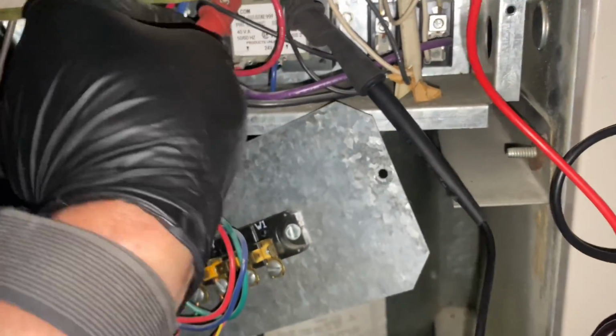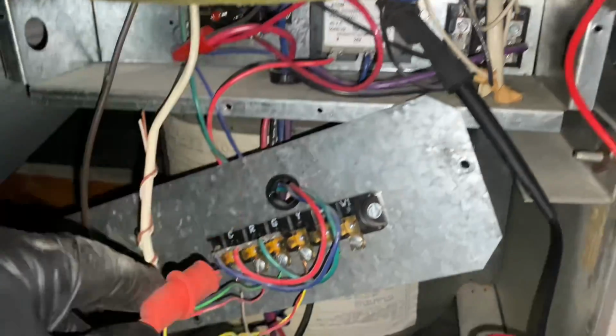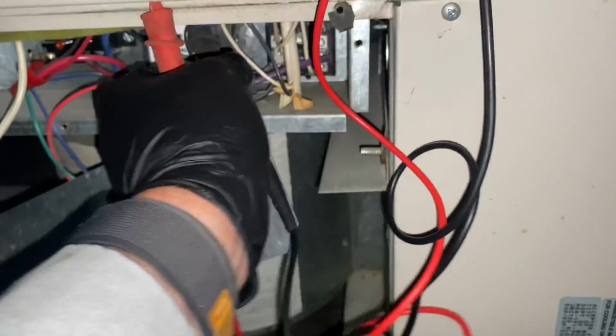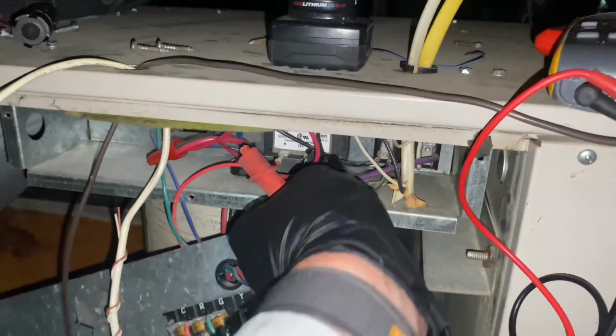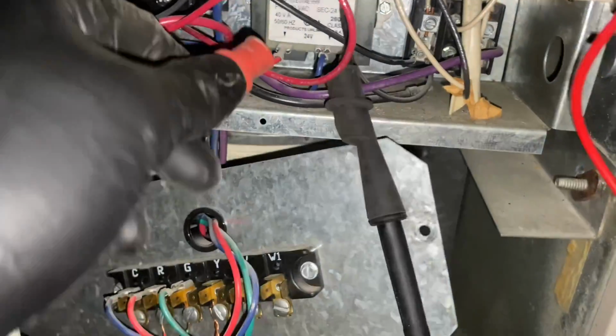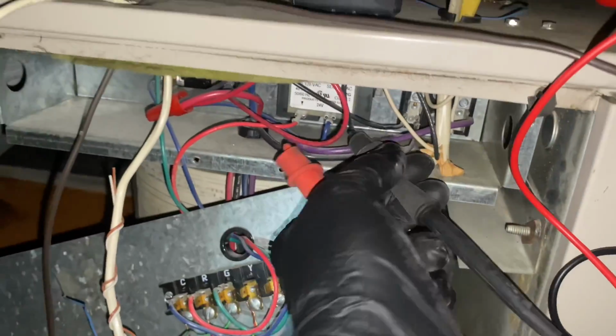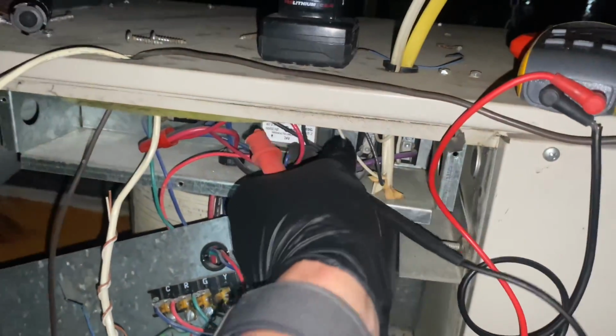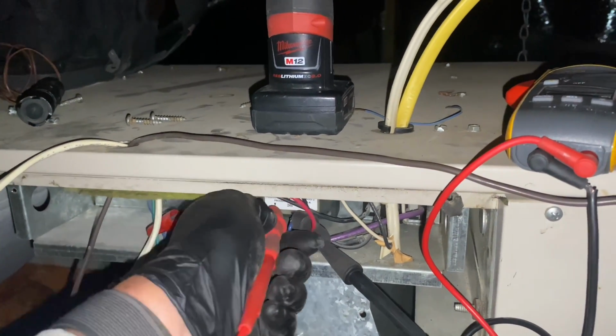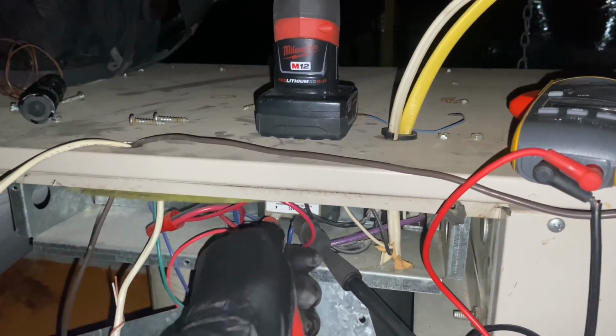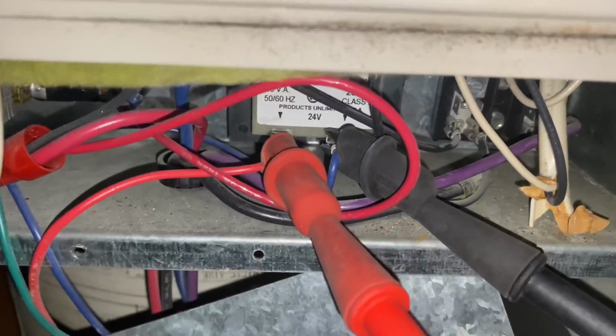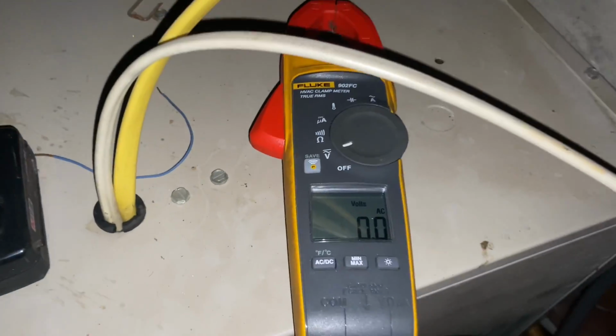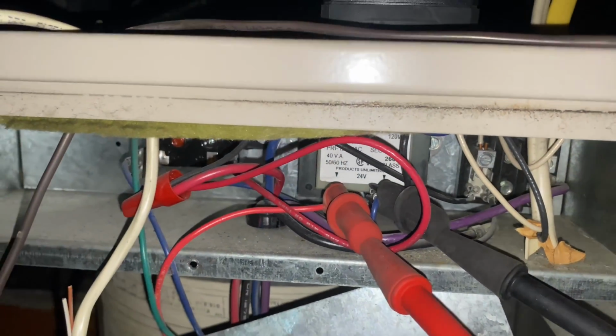So now let's carefully test and see if we have a short between the transformer and the control board. So let's take off those two probes right there. Let's put one on common. Oh, come on. Stay on there, buddy. Okay, one right there. And another one right there. Come on. Get on there. Okay. And we have nothing. We have no voltage leaving the transformer. So, we have a defective transformer.